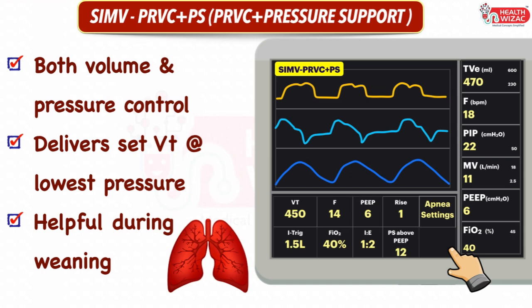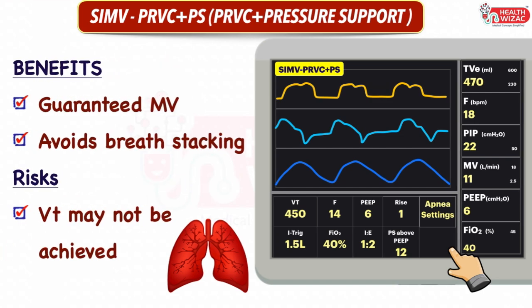SIMV PRVC plus pressure support is a mode that allows control of both pressure and volume settings. The ventilator delivers a preset tidal volume at a set rate with the lowest possible pressure, thus avoiding the risk of barotrauma. This mode is very helpful during the weaning process. Advantages include guaranteed minute ventilation and reduction in breath stacking, whereas risks include non-delivery of preset tidal volume sometimes.